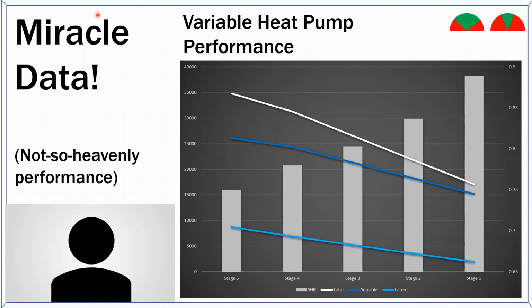And so what happens - by the way, you also aren't changing the size of the coil as you reduce this capacity, which means that surface area is absorbing heat very quickly because it's oversized for what its needs are, which means it takes longer for it to get really cold. So even if you didn't game the SEER game, you would still have a little bit of this effect, because what this is, is high stage and low stage.